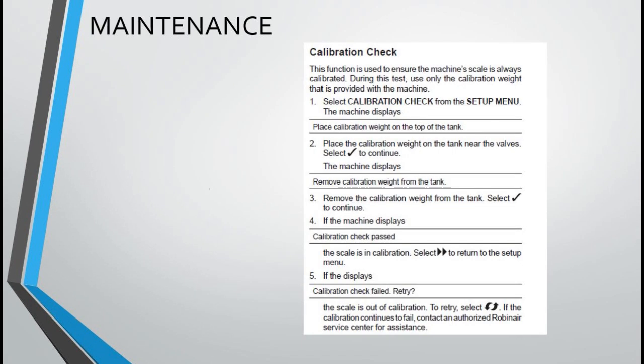Calibration check. Select calibration check from the setup menu. Place calibration weight on the top of the tank. Place the calibration weight on the tank near the valves. Select check to continue. Remove the calibration weight from the tank. Select check to continue. If the machine displays calibration check passed, the scale is in calibration.